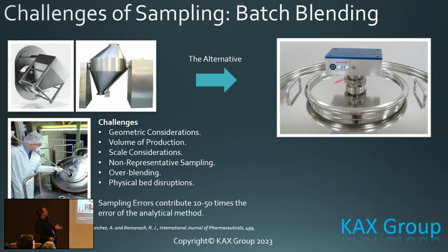So what do we do? Okay, we go to an inline NIR system. That gives us a measure of the sample as it exists in the process at the point of time. Is that a 100% statistically representative sample? No. It's still a grab sample. How do we turn it into a statistically representative sample? As Phil and Steve said, we need to understand how many spectra need to be taken to represent a unit dose. Then it becomes a composite sample. And that composite sample is much more representative than your single spectral grab sample.